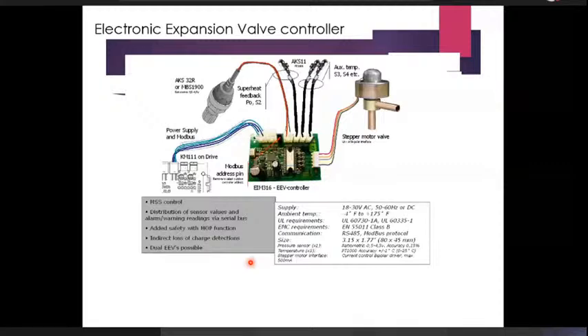Now this diagram shows us some of the interconnections and interrelationships. The expansion valve controller is right here. Then this is going to take some feedback from here as well. The evaporator coil is fed from the expansion valve, so refrigerant comes in here, and from here it goes to the suction of the compressor. We need to sense the temperature and pressure at the outlet of the evaporator, before the refrigerant goes to the compressor, so we need a pressure sensor and a temperature sensor. And as I mentioned before, all of these need to be integrated. So we need a discharge pressure sensor, and we need a surface temperature sensor for the discharge gas.